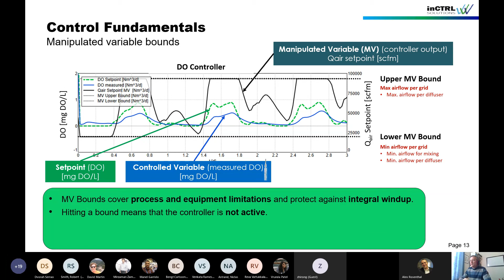Also important, just from a conceptual understanding, is that if you are hitting a bound, that controller is not active anymore. It's just running on a fixed value. Overcoming manipulated variable bounds must be done outside the controller, which means you can retune whatever you want, there is no improvement in performance. The only exception would be if the controller is tuned way too aggressively, so that you have an oscillation and that's the reason you are hitting the bound. But if you are continuously hitting a bound like you see here, you cannot solve that by changing the tuning. Very important so that you know what causes it and how you can overcome it.